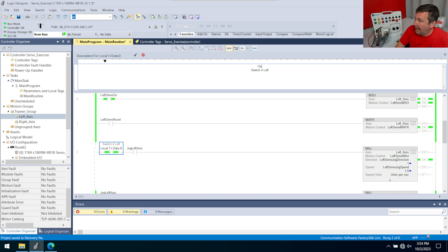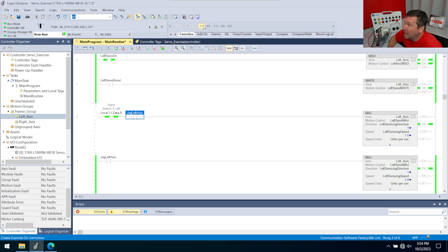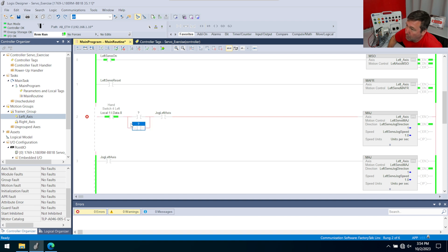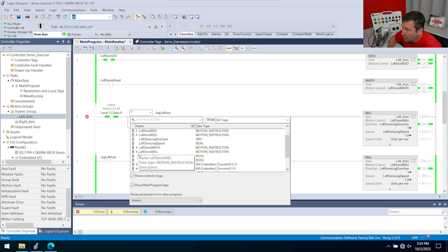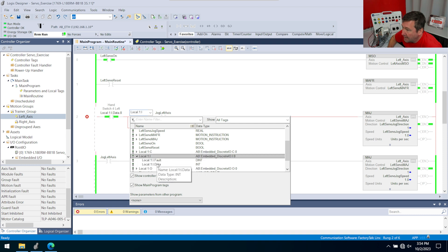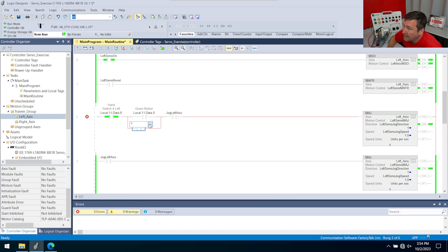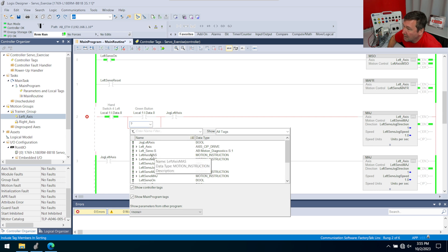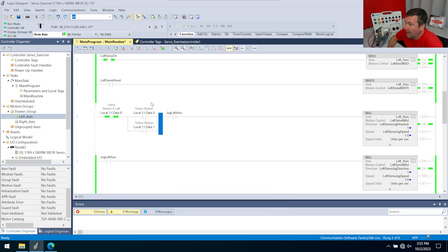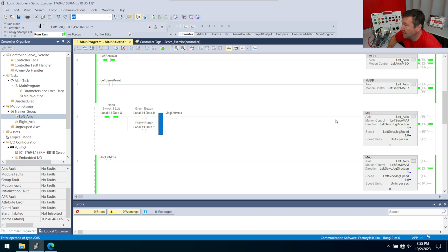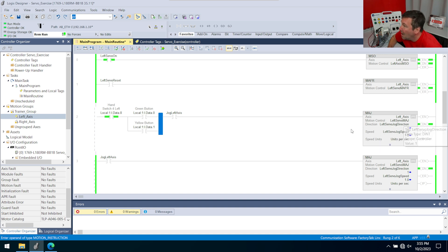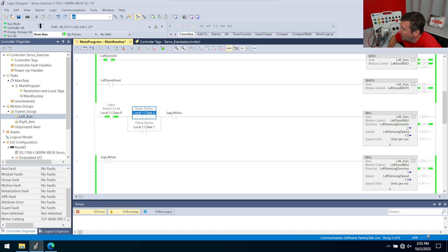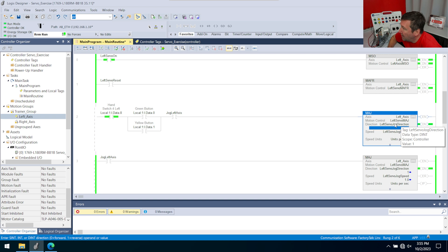Then we have the green button or the yellow button. So I'm simply going to bring another go look for a one examine on down. We'll put a branch around it and bring another one down into this lower branch. So this will be our green button. So that'll be local colon one colon I data zero. Then the other one will be local colon one colon I data one. Most people think that the output instructions have to go on the right side of the rung, but we can actually put output instructions in the middle here and it'll continue to pass through. So green is supposed to be counterclockwise, and we know counterclockwise is a value of one in this left servo jog direction.